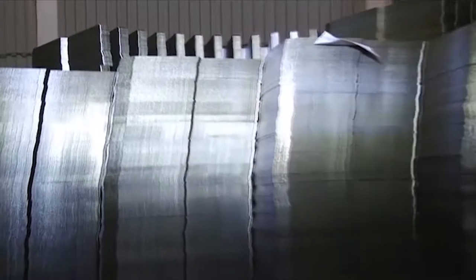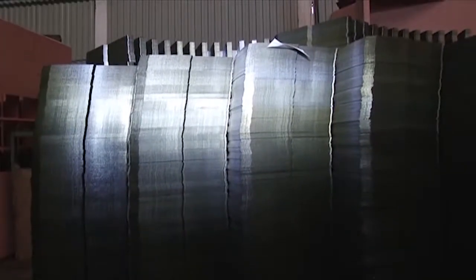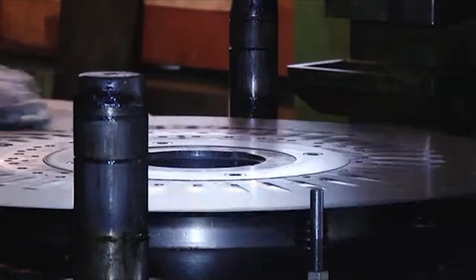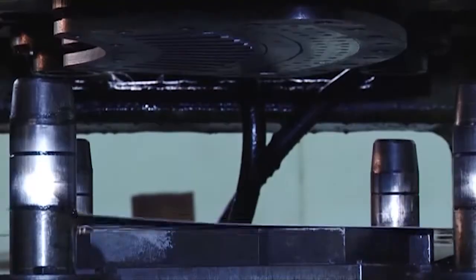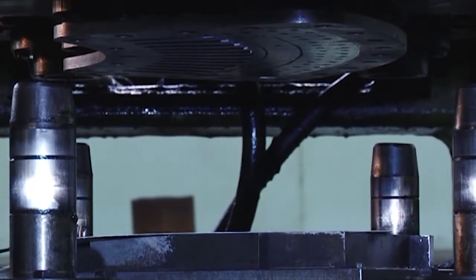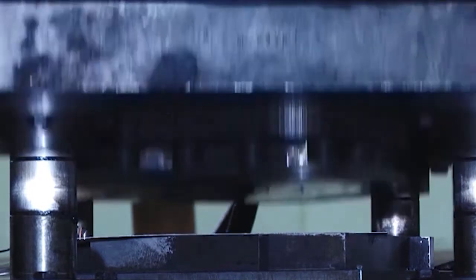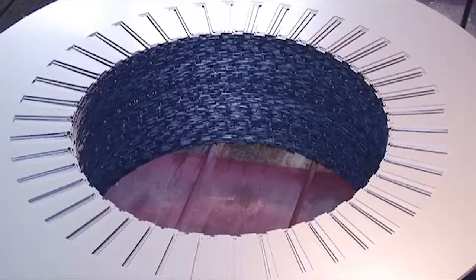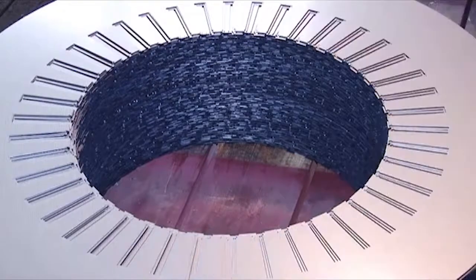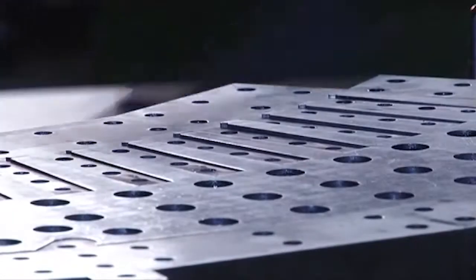Various methods are used to manufacture the segments. One of these methods is stamping. The stamping machines, with a maximum capacity of 800 tons, stamp segments or round hole sheets in the case of small dimension motor assembly out of steel rolls. There are slots on the outside of the segments which are later used for copper winding installation.